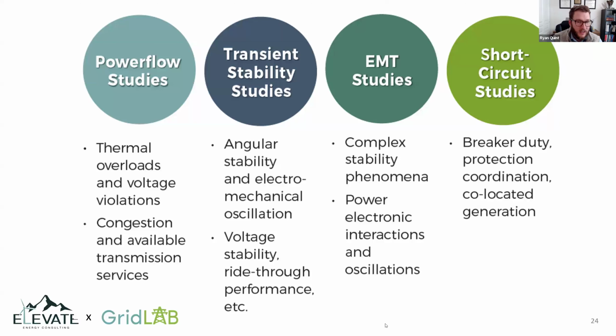And then we've got the EMT studies, which are rather complex, looking at complicated stability phenomena around controllers, phase lock loops, lots of power electronic interactions, and potentially the subsynchronous oscillations, which are very concerning for synchronous generators and nearby series compensated lines, where we see very quick instabilities that can lead to potentially very costly damages.